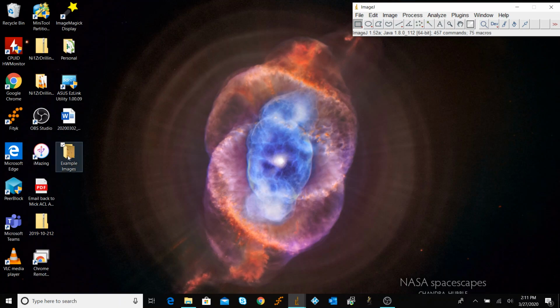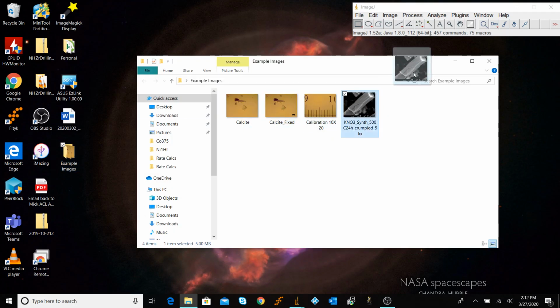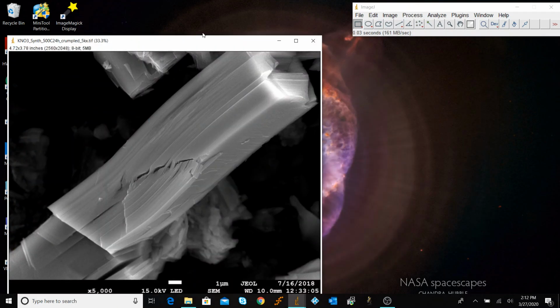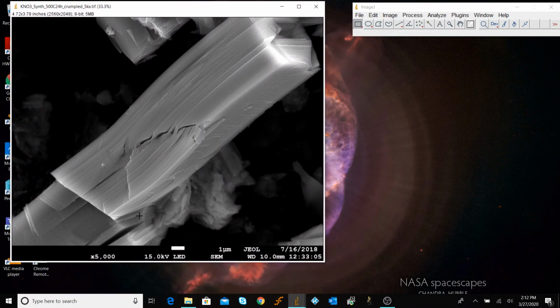So the main difference between the optical microscope and the SEM is that an SEM image already has a scale bar embedded. So here we can see that the scale bar is embedded in the image, but the problem is that we do not want all of this extra information because it is essentially meaningless to us. So magnifications are typically meaningless. The accelerating voltage is slightly important, as well as the working distance and the detector that we're using.